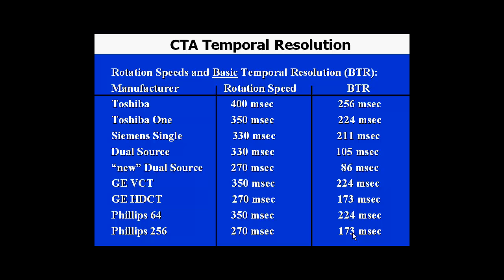These are examples of temporal resolution for a variety of scanners currently available on the market, from Toshiba, Siemens, Philips, and General Electric. Rotation speed could range from as slow as 400 milliseconds to as good as 270 milliseconds. The basic temporal resolution — looking at 180 degrees plus the 50 degrees of fan beam width — is given in the column on the right.